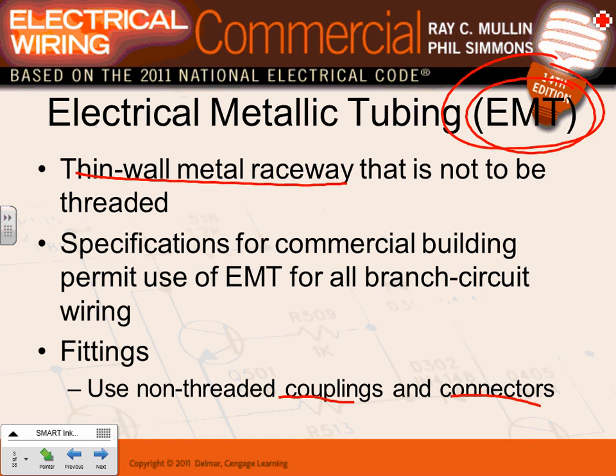Here's the minimum use case: if you have a feeder, minimum you have to use EMT - unless you have severe physical protection needs. Can you use EMT for branch circuits? Yes. What's the alternative for branch circuits? MC cable. But for feeders in a commercial building, you almost must put them in an EMT conduit. Non-threaded compression and non-compression type connectors are used - no threading at all.